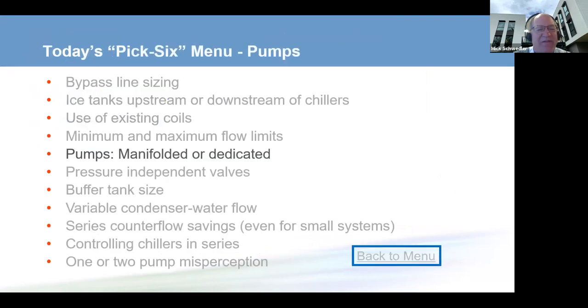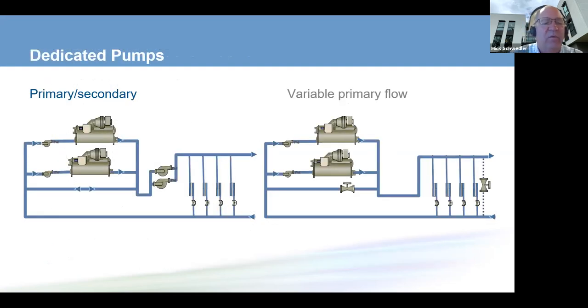Next up, should we manifold pumps or should we dedicate them? And when I'm asked by an engineer or a customer, I never tell them which way because I always guess wrong for them for a particular reason. So we're going to talk about the advantages and disadvantages of both dedicating pumps and manifolding pumps. So quite often we see dedicated pumps, or pumps dedicated to each chiller, in a primary secondary system. So in this case, we have a primary pump per chiller. When we turn a chiller on, we turn its pump on. Pretty simple. In a variable primary flow system, we may also have dedicated pumps for chillers. And in this case, when we turn a chiller on, we turn its pump on.